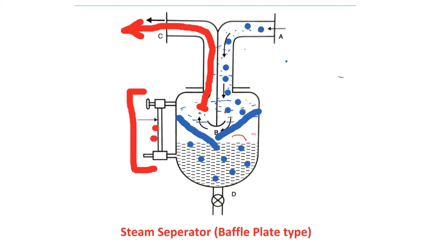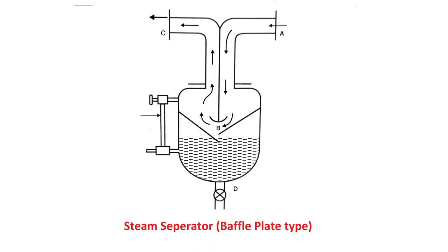The water collected in the vessel is removed at intervals through the drain pipe D. Whenever sufficient water has collected in the steam separator, it is removed via drain pipe D. So the working principle of the steam separator is very simple: due to inertia and density difference, water particles and steam are separated. Water particles, being denser, fall down and are collected in the vessel.